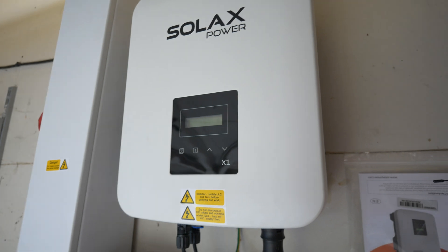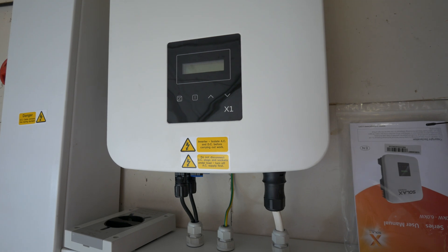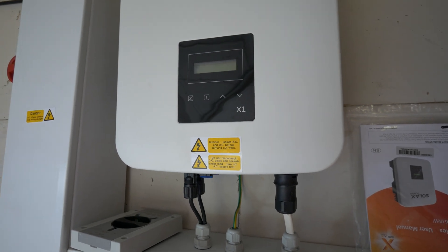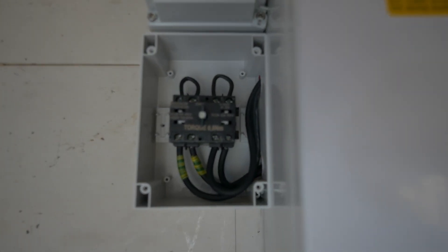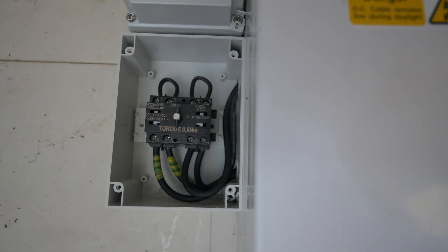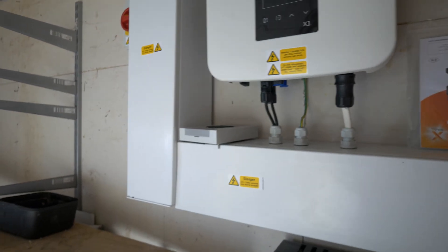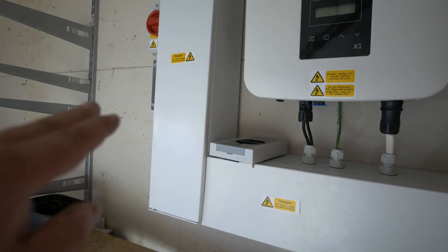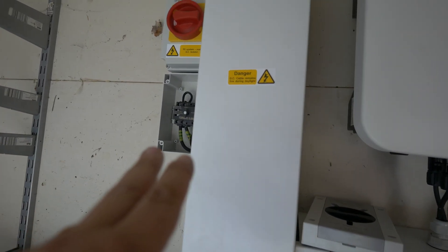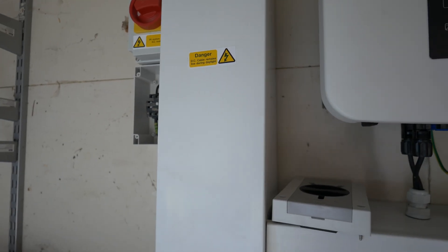When the inverter's on the floor, where's your isolation point for your strings without it? If you're using optimizers from SolarEdge, for example, it's less of an issue — but still, it makes perfect sense to put a point of isolation in the wiring system. I don't fall for the rubbish around these being dangerous — it's the people wiring them up incorrectly that's dangerous, and that's the problem we need to solve, not removing them just because of that problem. You can have the same issue with your MC4 connectors and the wiring systems on the roof. If people aren't capable of wiring up DC isolators, industry's got a far bigger problem than simply removing them from the DC strings — it's a ridiculous concept.